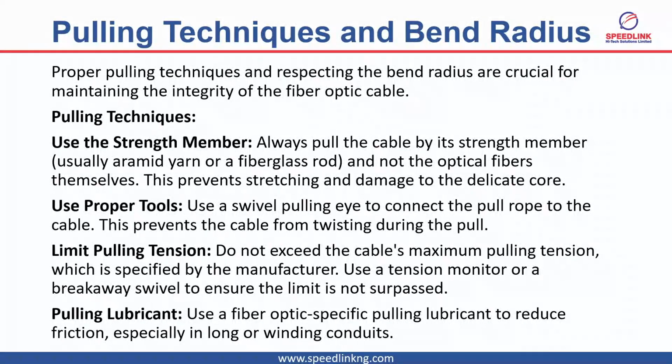Now, as you're pulling them inside the duct, you have to make sure that you're not pulling the cable more than what the cable can withstand, isn't it? Because if you pull the cable with a force that the cable cannot withstand, you can damage the cable inside it. Because as you're pulling it, maybe something freezes the cable, and that tension is still pulling the cable. Before you know, you cut the cable inside the ground, and you don't even know where it happened, right? Which will damage the work.